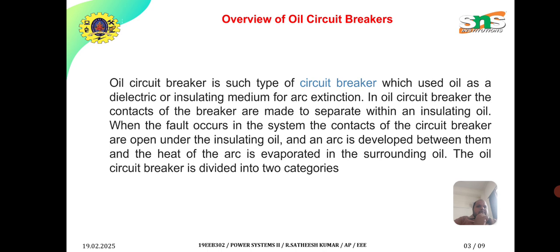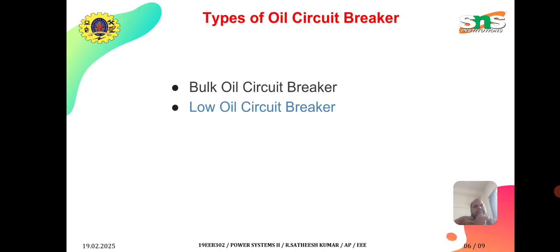The oil circuit breaker is divided into two categories. One is the bulk oil circuit breaker, the other is the low oil circuit breaker. As the name implies, a bulk oil circuit breaker uses a larger amount of oil as the dielectric medium. The low oil circuit breaker uses less oil, and another name for it is the minimum oil circuit breaker.